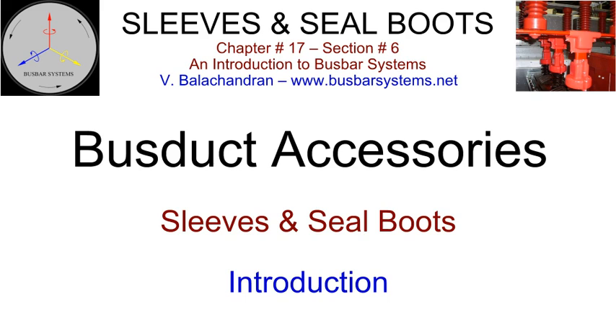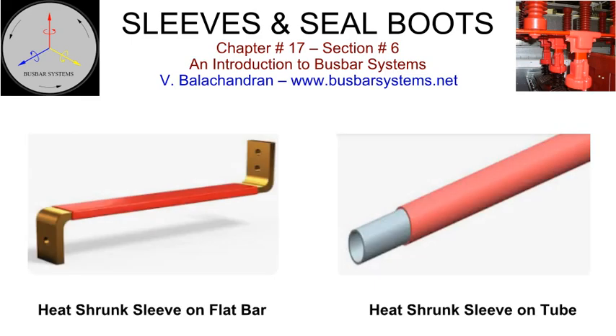The thickness, as well as the overlap with the insulated bus bar, must be carefully considered. The thickness and overlap increase with an increase in the rated voltage and basic insulation level. Sleeves. Sleeving of bus bars has been practiced in low voltage applications, less than 1100 volts, in switchgear panels and bus ducts. Since the recommended air clearances and creepage distances are quite small in low voltage equipment, sleeving is an excellent backup for an inadvertent weakening of insulation due to the ingress of dust, moisture, and vermin.